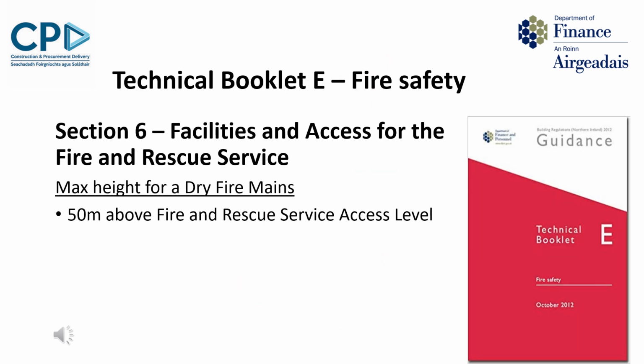The third item that has been amended in Section 6 sets a new maximum story height for provision of dry fire mains. TBE previously required the provision of wet fire mains where a building has a story more than 60 metres above fire and rescue service access level. The amendment reduces that threshold to 50 metres maximum above fire and rescue access level for provision of dry fire mains. Buildings with a story more than 50 metres above fire and rescue service access level now require wet fire mains.